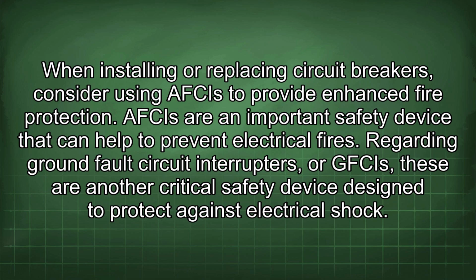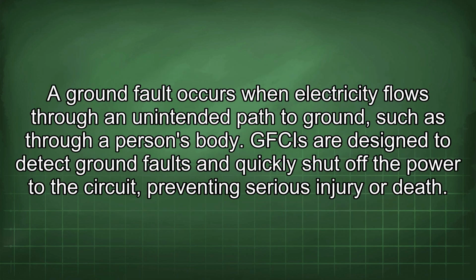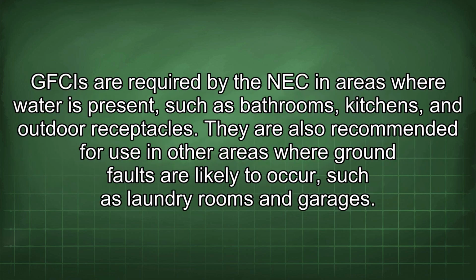Regarding ground fault circuit interrupters, or GFCIs, these are another critical safety device designed to protect against electrical shock. A ground fault occurs when electricity flows through an unintended path to ground, such as through a person's body. GFCIs are designed to detect ground faults and quickly shut off the power to the circuit, preventing serious injury or death. GFCIs are required by the NEC in areas where water is present, such as bathrooms, kitchens, and outdoor receptacles.